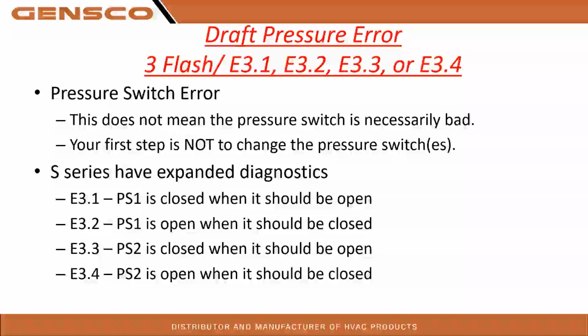maybe even the wires for pressure switch 1 and 2 got swapped. So start looking at it holistically and then trying to figure out, okay, is pressure switch 1 actually pressure switch 2 wires? Did the wiring get switched? Maybe the tubing is not where it should be from either the manufacturer or from the installers. So just step back, get the install guide or service facts, and make sure everything is where it should be. Grab your wiring diagram and go, yeah, okay, orange and purple go to pressure switch 1 and blue and yellow go here, and just look at it holistically, right? So hardly ever the pressure switch.